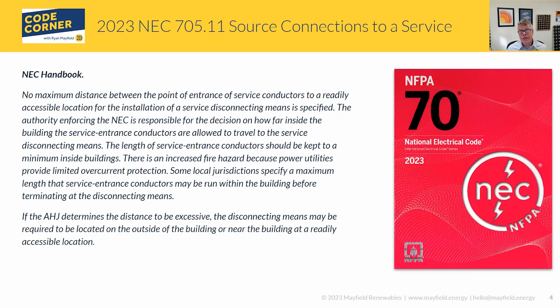The AHJ is responsible for deciding how far those conductors can travel. The handbook even notes that you want to limit them inside the building since they're not protected, which gets back to what 230.90 says about the overload protection function of these overcurrent devices. All in all, if you can keep it to the lengths that were in 2020, that's great. But in 2023 we've been allowed greater distances — just work with your AHJ to figure out what's considered excessive and what's appropriate for that installation.